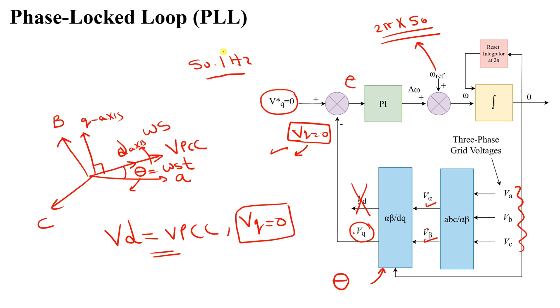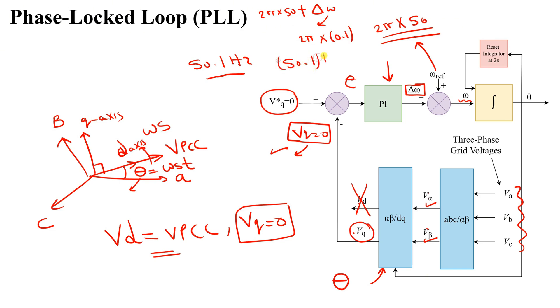The deviation from the reference frequency, denoted delta omega, is obtained through the PI controller. The PI controller takes the error between VQ and the VQ reference of zero and gives us a signal delta omega. By adding omega reference (2π × 50) plus delta omega, we estimate the actual grid angular frequency — for example, 2π × 50.1 Hz if the grid frequency is 50.1 Hz instead of 50 Hz.